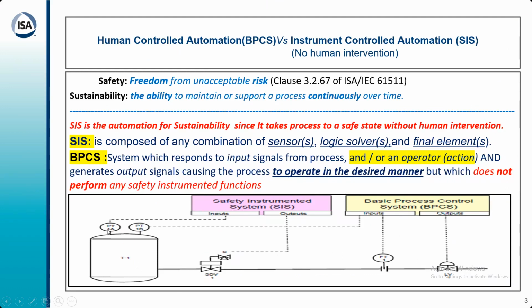SIS can fail. It has a transmitter and a solenoid valve. A solenoid valve can get stuck. You are ultimately using air, and air can have debris and probably moisture, which can make the solenoid valve fail, and then SIS can also fail. So SIS can also fail, remember that. The only thing is that SIS has the flexibility that you can have a higher level of SIS. Instead of SIL 1, you go for SIL 2 or SIL 3 at maximum. It will cost you money, but you can have a higher level. So it is a flexible way of addressing a higher level of risk than what is addressed by BPCS.